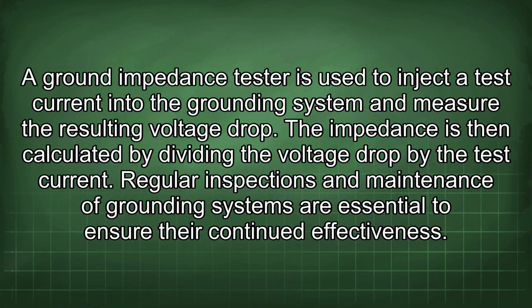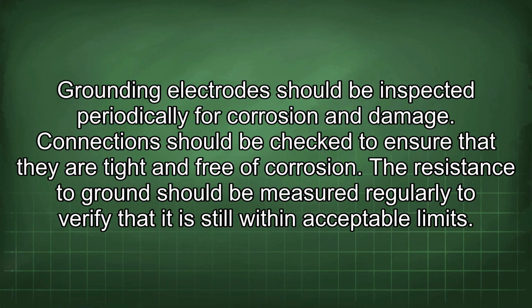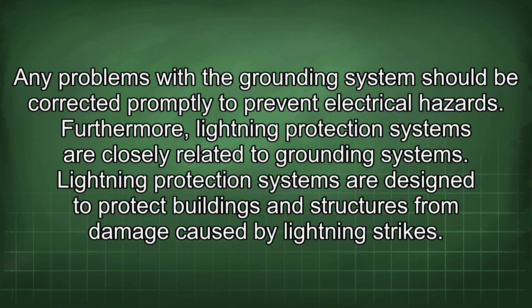Regular inspections and maintenance of grounding systems are essential to ensure their continued effectiveness. Grounding electrodes should be inspected periodically for corrosion and damage. Connections should be checked to ensure that they are tight and free of corrosion. The resistance to ground should be measured regularly to verify that it is still within acceptable limits. Any problems with the grounding system should be corrected promptly to prevent electrical hazards. Furthermore, lightning protection systems are closely related to grounding systems.